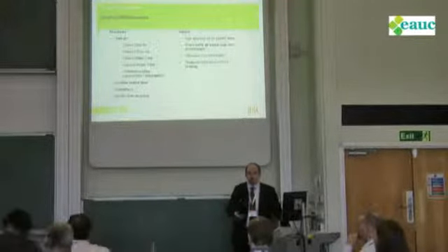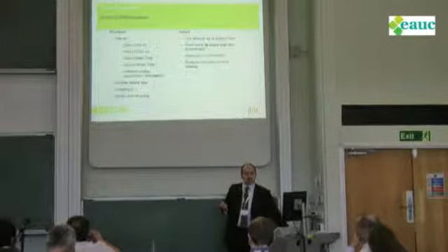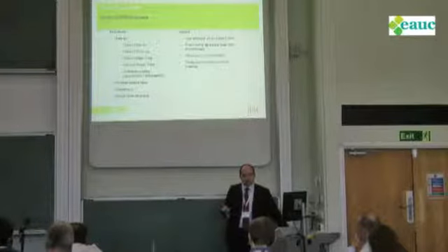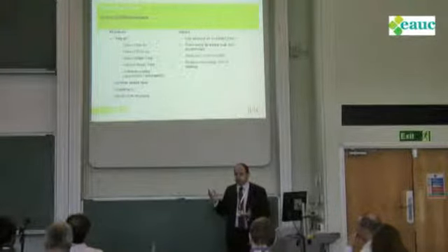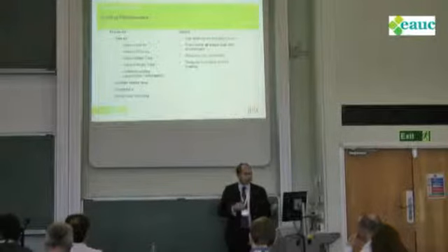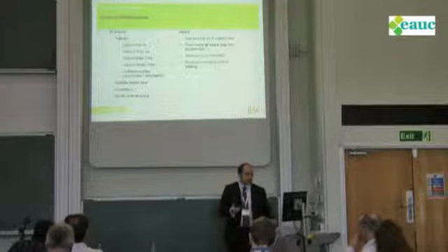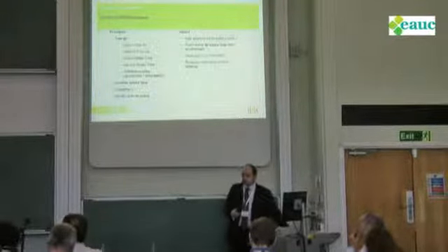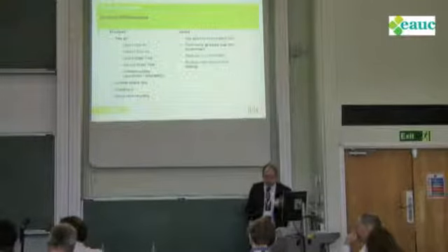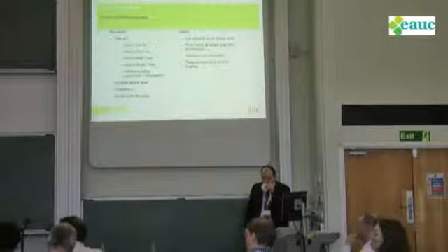Humidifiers, do you really need to humidify or dehumidify your data center? Most servers these days have such a wide tolerance for humidity that, unless you're using direct free air, you probably don't even need to switch your humidifiers on, saving you a lot of money. And again, Steve, I'll just add, the last probably 5 data centres that we've completed at Future Tech, we don't have any humidity control in the rooms.